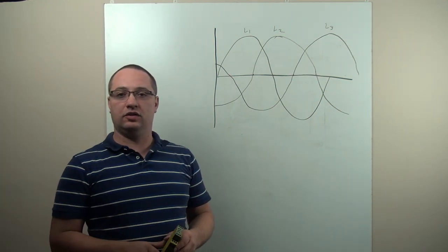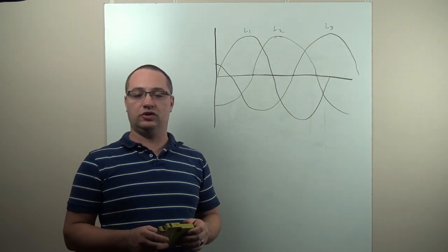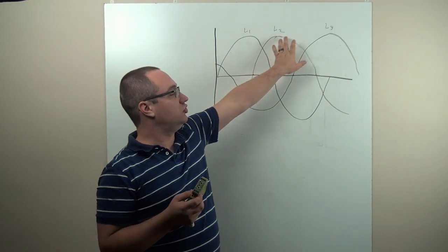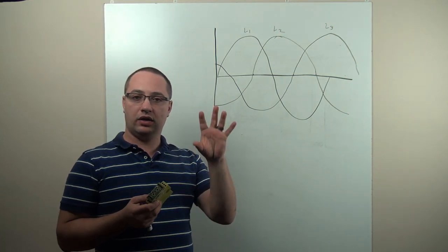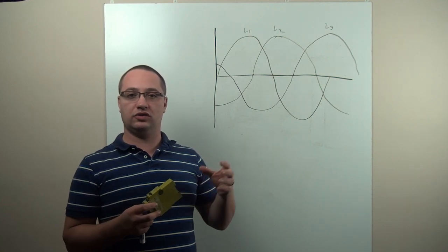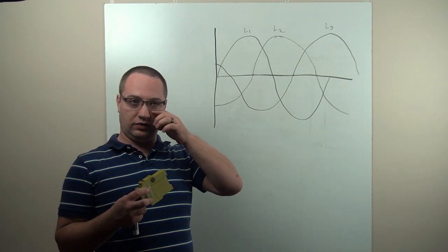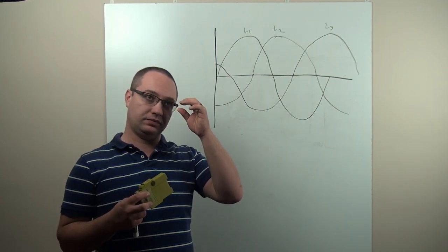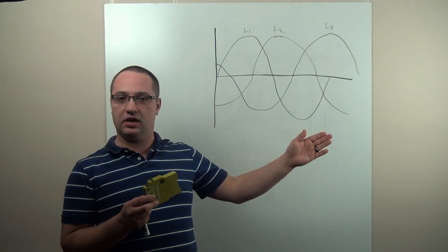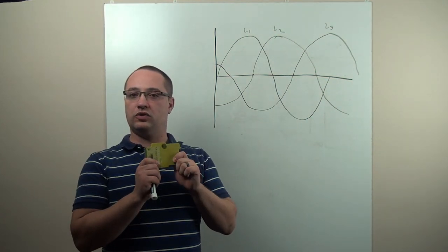Now that we've gotten that little introduction out of the way, what does a power quality relay actually do? This relay monitors the three phases, L1, L2, and L3, and it controls a set of contacts. Those contacts generally run some sort of large contactor in the machine, whatever that industrial machine happens to be, and they will only allow the power to go past that contactor, meaning to power everything else in the machine, if the power is good.